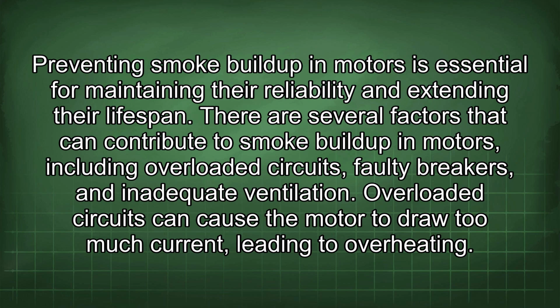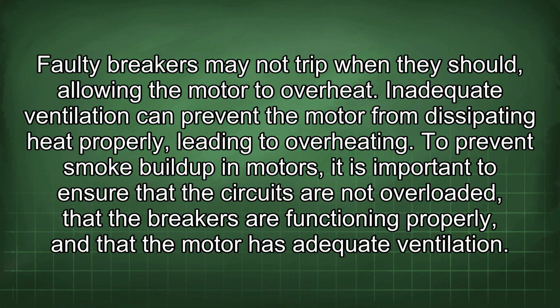There are several factors that can contribute to smoke buildup in motors, including overloaded circuits, faulty breakers, and inadequate ventilation. Overloaded circuits can cause the motor to draw too much current, leading to overheating. Faulty breakers may not trip when they should, allowing the motor to overheat.